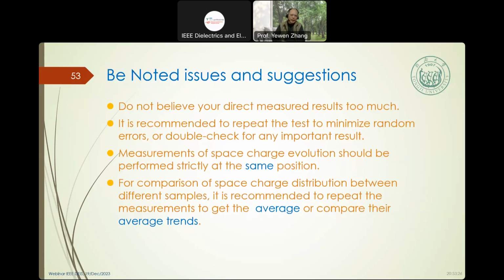So this gives us some notes on insulation issues and suggestions. Do not believe your direct measurement result too much. It's recommended to repeat the test separately to minimize random error, or double check any important result. The measurement of space charge evolution should be performed strictly at the same position. It's important. For comparison of space charge distribution between different samples, it's recommended to repeat the measurement to get the average, or compare their average trend. So you cannot measure it one by one. It needs averaging.